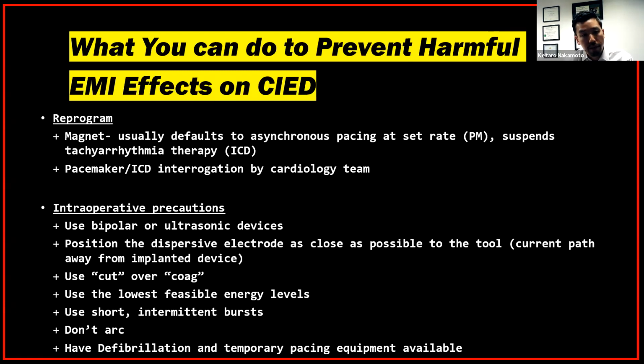The intraoperative precautions you have to follow: try to use bipolar or ultrasonic devices instead of monopolar Bovie devices when possible. Position the dispersive electrode as close as possible to the active electrode. Make sure the current path is away from the implanted device. Use cut over coag, use the lowest feasible energy levels, use short intermittent bursts like we talked about, don't arc, and have a defibrillator and temporary pacing equipment available in the OR.